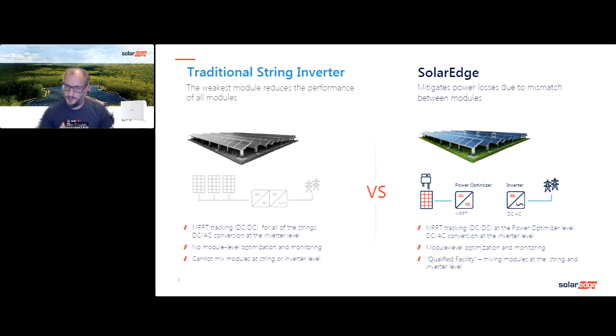And so that provides that string stretching feature that I talked extensively about previously, but it also provides the ability to do local MPPT for those 2 modules. And, depending on the amount of undulation you have in the land, which is that nice gentle slope, sloped land that a lot of times we see in the Northeast and the Pacific Northwest, that slope will cause a change in azimuth and in direction, which will natively impact your maximum power point tracking, where you are in that IV curve of those modules. And so providing that on the module level, that 2 to 1 module level, really provides the most energy throughput that you can get.